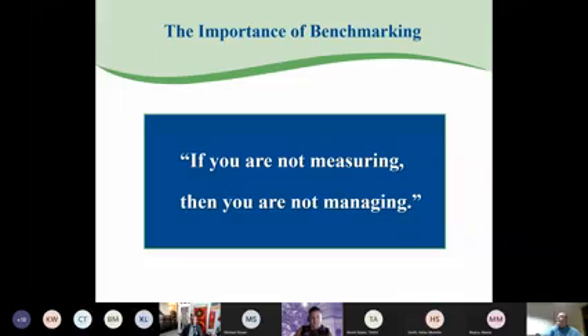So a little deeper, you can take those benchmarks and look at HVAC systems, motors, frequency drives, substations, compressed air, lighting, and look for opportunities to save. Benchmarking energy can then be charted against the cost to produce your product or financials or output using units of production. What is your unit of production? With that, once you know that, you can chart the cost in kW per pound or dozen or unit, kW demand and distribution, load factor and utilization, which is how well we're using power, develop a cost per day, kWh per day, etc.